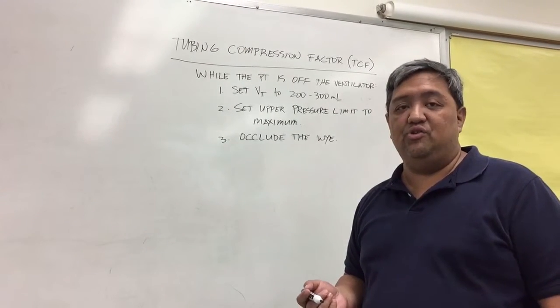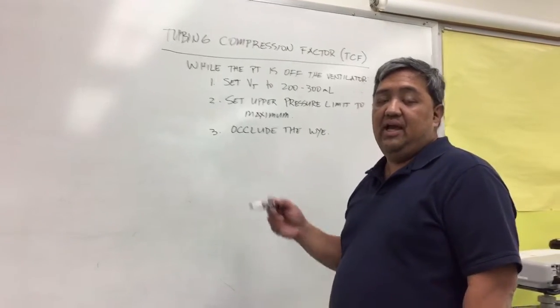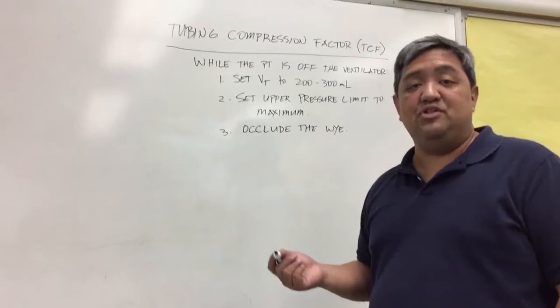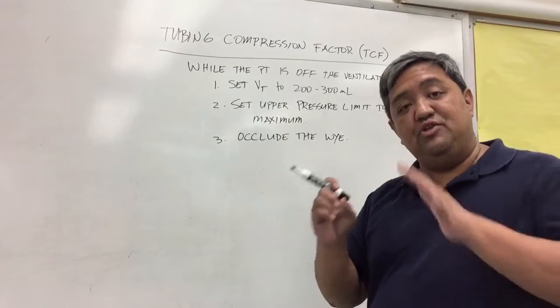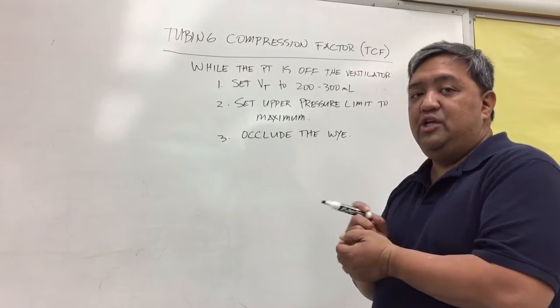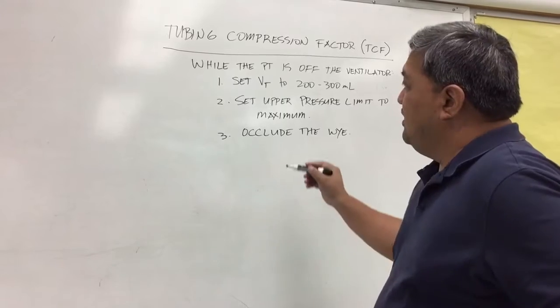We want to set the tidal volume to about 200 to 300 mls, and then set the upper pressure limit to maximum. Then we need to occlude the Y.